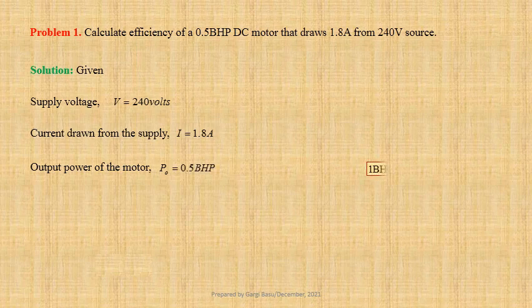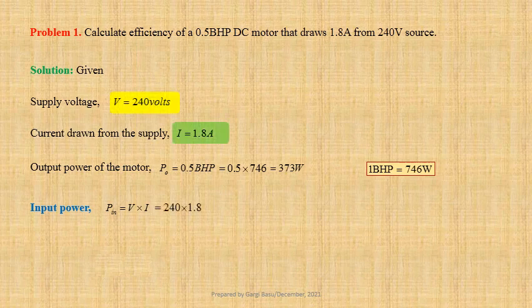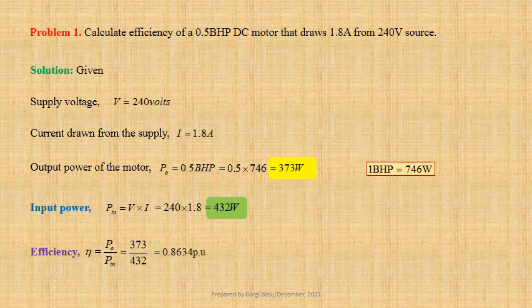Since 1 BHP equals 746 watts, P_o equals 0.5 into 746, that is equal to 373 watts. Let us first calculate input power: P_in equals V into I. Using values we get 240 into 1.8, that is equal to 432 watts. Efficiency of the motor: eta equals P_o divided by P_in. Using values we get 373 divided by 432, that is equal to 0.8634 per unit or 86.34 percent.